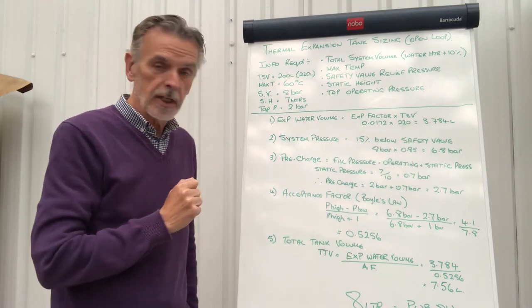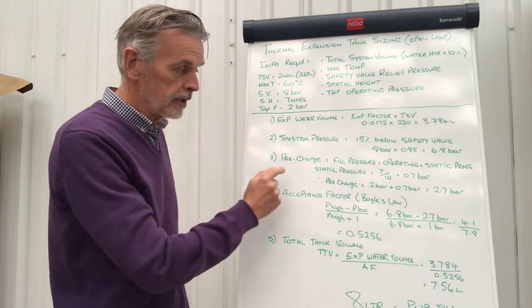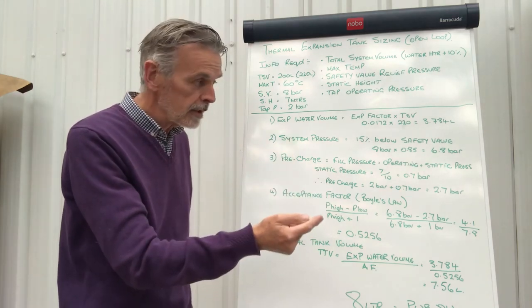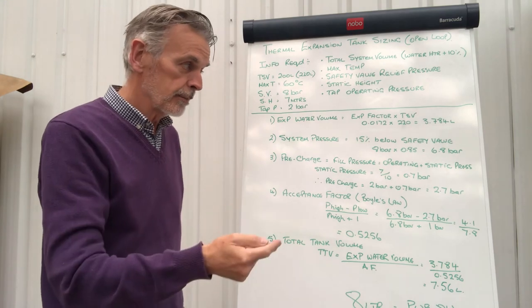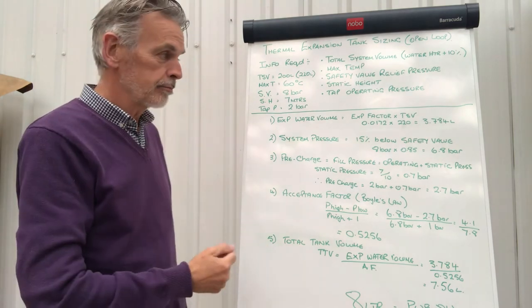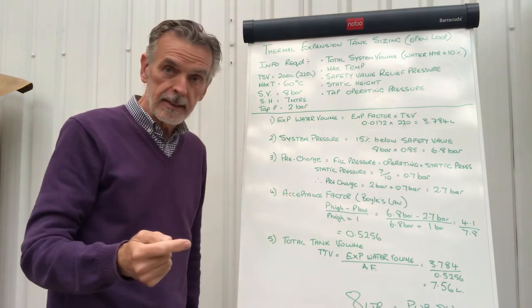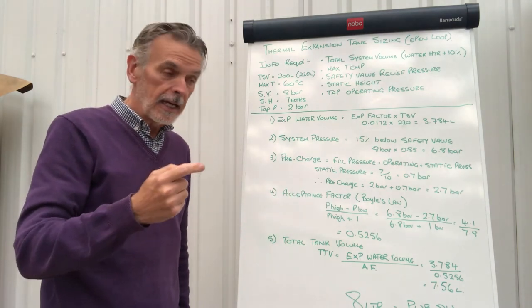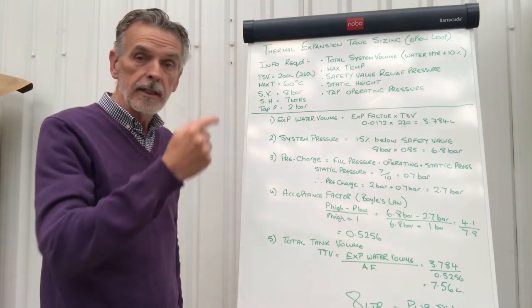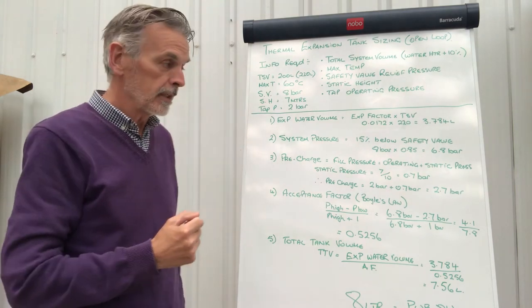Let's calculate now the pre-charge of the expansion vessel. So the pre-charge is equal to the fill pressure, which is equal to the operating pressure plus static height pressure. So the static pressure, as I said to you before, is the height to the furthest, the highest discharge point in the building.